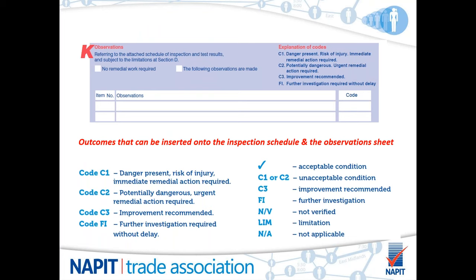Now, as you can see, we've got a list of the codes there. So a C1 or C2 would indicate an unacceptable condition. C3 would be an improvement required. FI is further investigation, which would again leave the report as unsatisfactory. And you have additional options such as not verified, limitation, or not applicable.